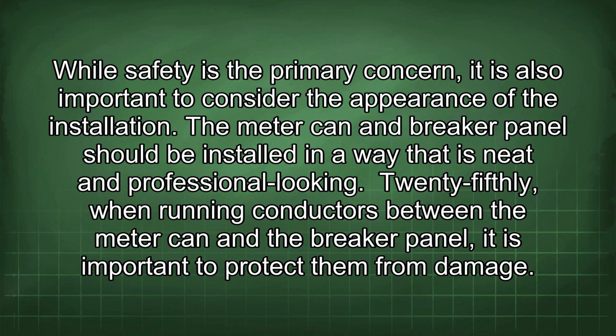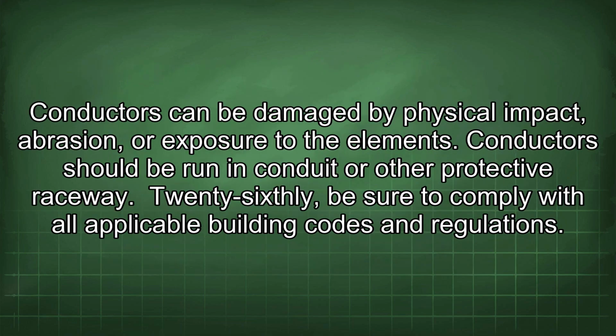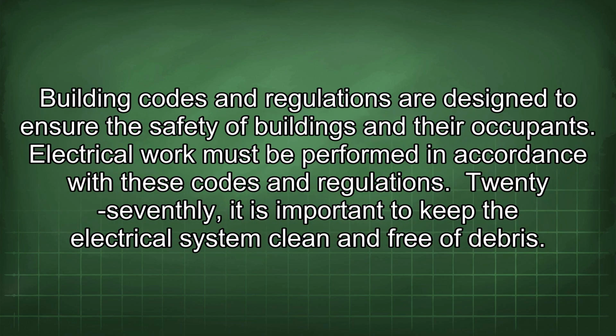25th, when running conductors between the meter can and the breaker panel, it is important to protect them from damage. Conductors can be damaged by physical impact, abrasion, or exposure to the elements. Conductors should be run in conduit or other protective raceway. 26th, be sure to comply with all applicable building codes and regulations. Building codes and regulations are designed to ensure the safety of buildings and their occupants. Electrical work must be performed in accordance with these codes and regulations.